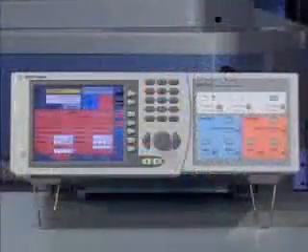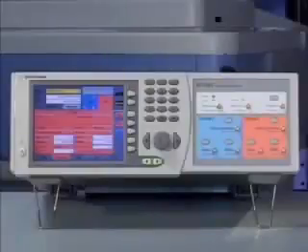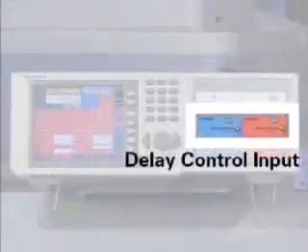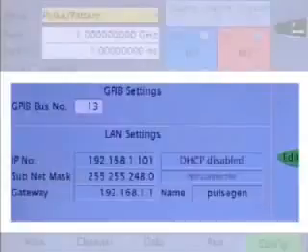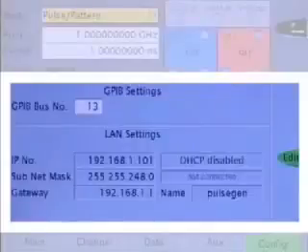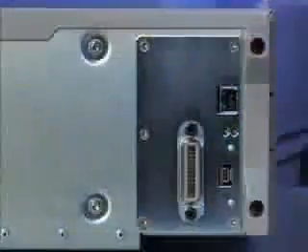On top of that, the 3.35 GHz pulse generators provide several inputs to use an external clock source, to start the output on a special trigger signal, or control the delay of the signal, which will be shown later in this video. These pulse and pattern generators also come with graphical user interface pages that allow the modification of all settings required for the remote control interfaces, which are located on the back side of the instrument.